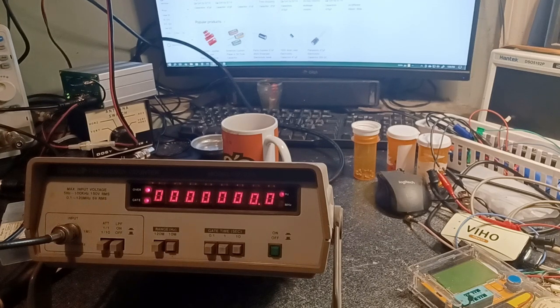So I must have hit her just right, because that's really good. But we've got to give her a couple of times to run through the gate time just to be sure. And there she just ran another one. Let it average itself out. But about an hour and a half's warm-up time. Well, maybe an hour and a half's warm-up time. So I'll know that it's got to be running at least an hour before I dare use it for any adjustments.